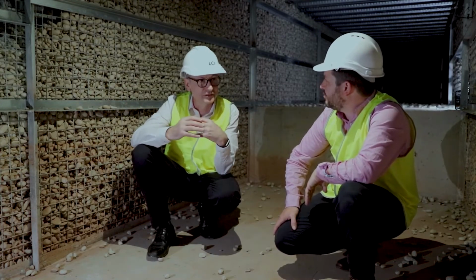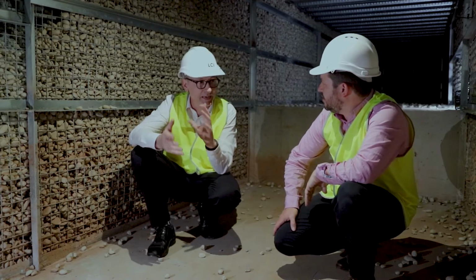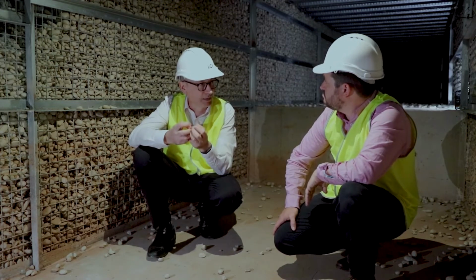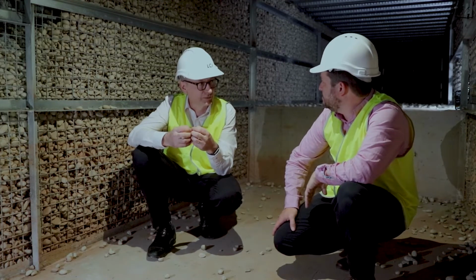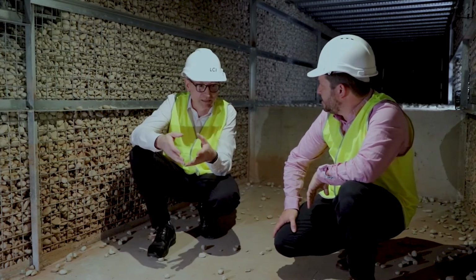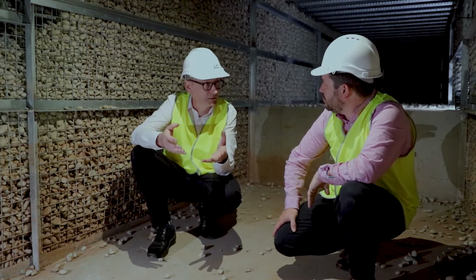When the 40 degree air passes over them, it engages with the stones and the pebbles, and they absorb a lot of the heat, leaving the air cooler. It must be a huge amount of surface area. Which makes it very efficient. It's very slow air moving, about 0.2 metres a second across it. And by the time the air gets to here from outside, it's already lost maybe 8 degrees. Wow, an 8 degree drop.